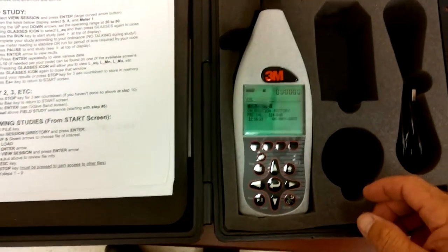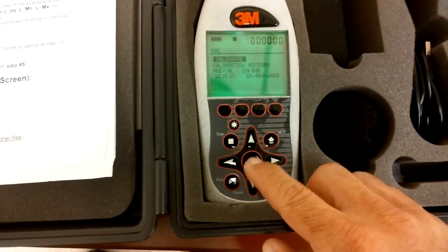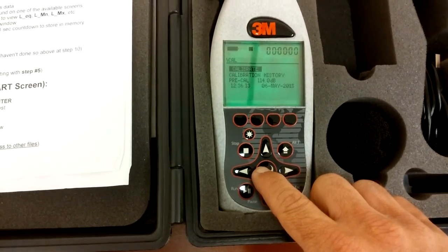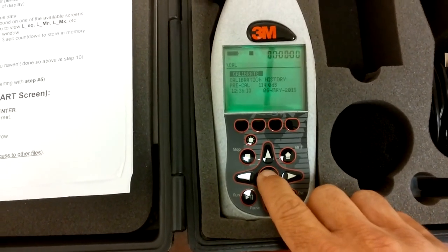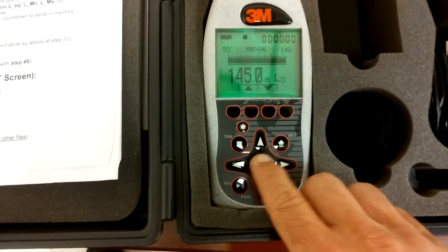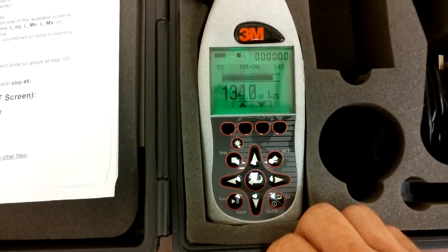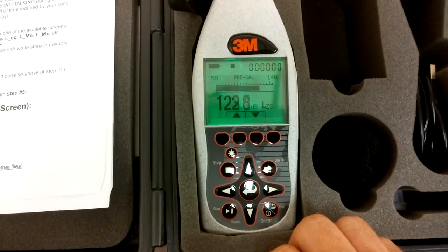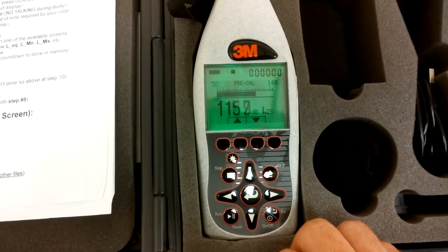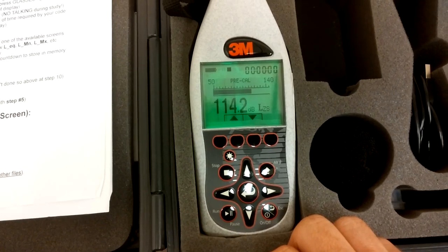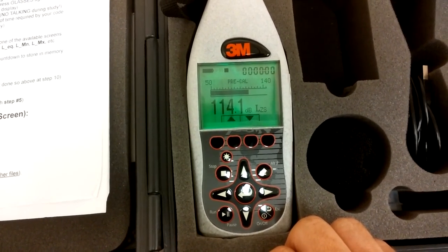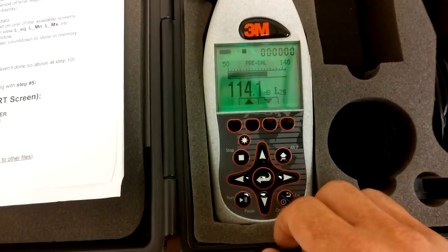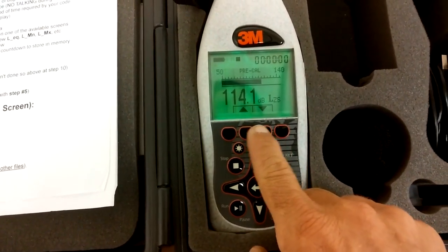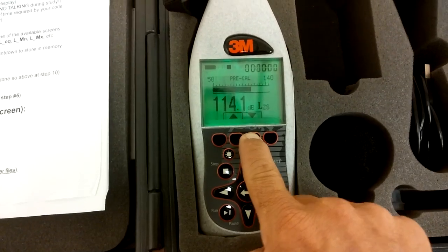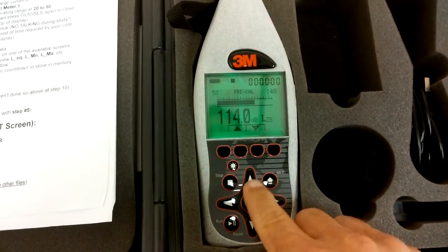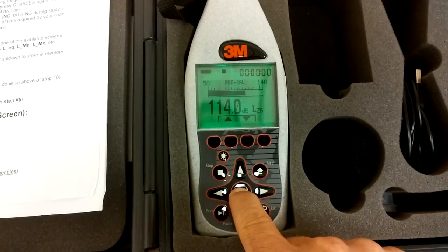And we'll come down, and on step number six, it says to press enter. Your enter button is this arrow that's directly in the middle. So we're going to start the calibration. You can see the meter counting down, and again, the calibrator is 114 decibels, so it should start registering close to 114 decibels. We're at 114.1, so we're going to bring it down using these arrows here. We want exactly 114, so I'll press the down button one time at 114. We're going to lock it in by hitting the enter button.